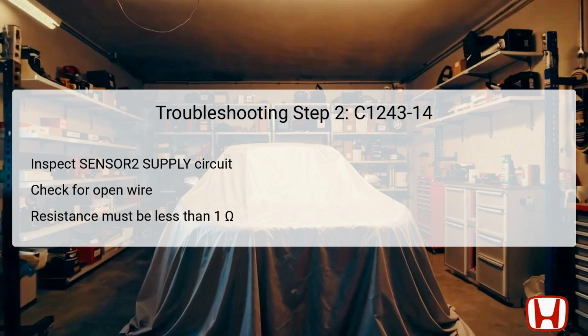Conduct an open wire inspection to check for any discontinuities that could cause signal failures. The expected resistance in the wiring should be less than 1 ohm, indicating a healthy electrical connection. If resistance is higher, it may suggest damaged wiring or poor connections. Detailed attention to the wiring integrity is essential because a compromised power supply can directly lead to low voltage signals and malfunctions indicated by the DTC. By ensuring that the wiring remains intact and well connected, you can eliminate common faults contributing to the error.